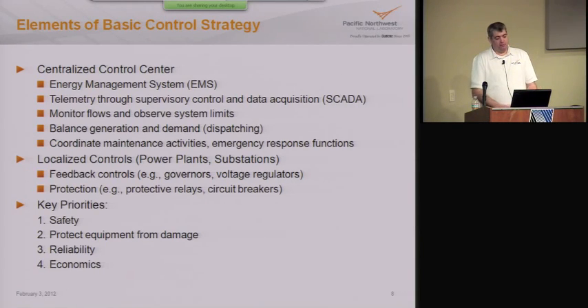And then when there's a problem, a blackout or some emergency, the control center is the place where that's coordinated from. But the real work, moment to moment, the closed loop feedback control that keeps the grid running, is mostly done at the local level. At power plants, for example, there are governors and voltage regulators that regulate the frequency and the voltage. If there's a fault on the line through lightning or short circuit or some other problem, there are protective relays at the substations that will detect that and trip the asset, either the power line or the generating plant, in real time, very, very quickly. Those are localized controls that work at that level.